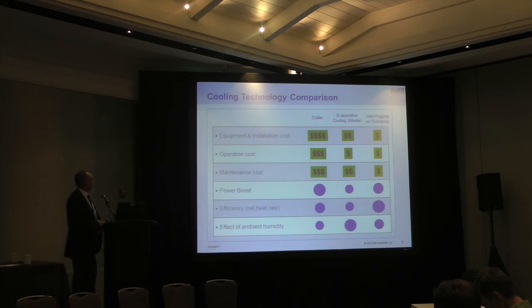This compares different cooling technologies. First, equipment and installation cost. We're comparing chillers, evaporative coolers, traditional media type evaporative coolers, and inlet fogging with overspray. So chillers are quite expensive, fogging is quite cheap. Operating costs, again, chillers are high, fogging is low. Maintenance costs, same thing. Power boost, if you do a lot of overspray fogging or wet compression, you can actually approach the power boost that you would get from a chiller, but of course for a fraction of the first cost and operating costs. And the efficiency or net heat rate, I think, might be slightly better with fogging and overspray, although you actually also should calculate the cost of the water, which becomes non-trivial when you're injecting 3% of the air mass flow as water.